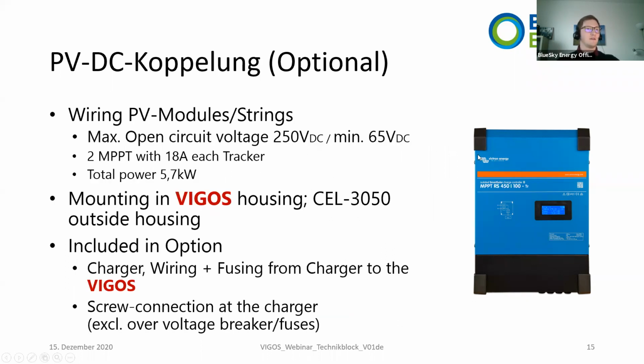This DC-DC charge controller has a maximum open circuit voltage of 450. Sorry again for the failure, there should be written 450 and not 250. So it's 450 volts input voltage. You have two MPPTs with 18 amps each tracker and a total power for two trackers of 2.7 kilowatts. So in total, 5.7 kilowatts. That means one tracker, for example, with 2.7 and the other with 3 kilowatts, so in total then the 5.7.